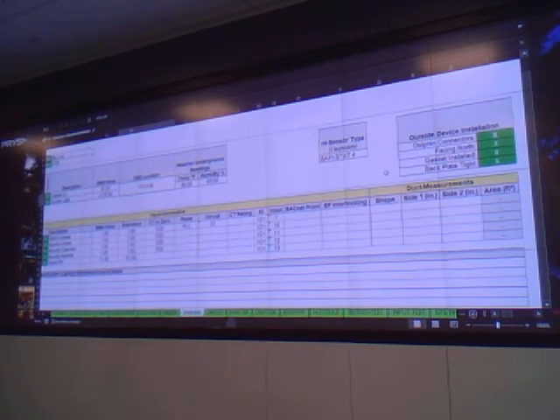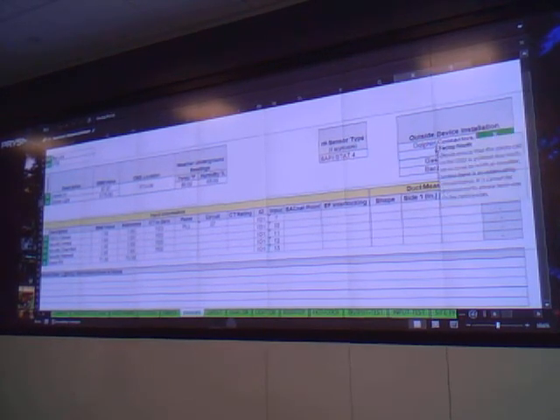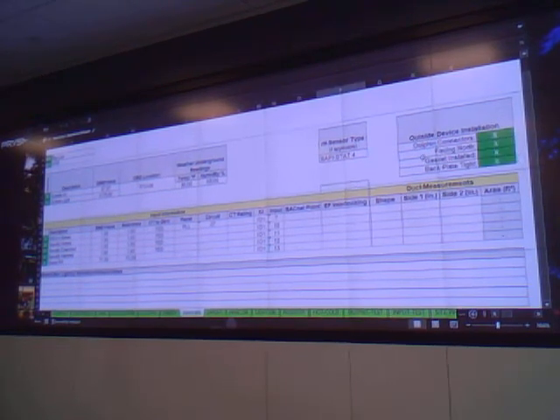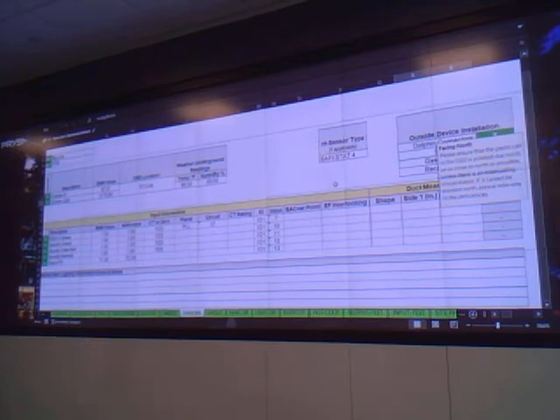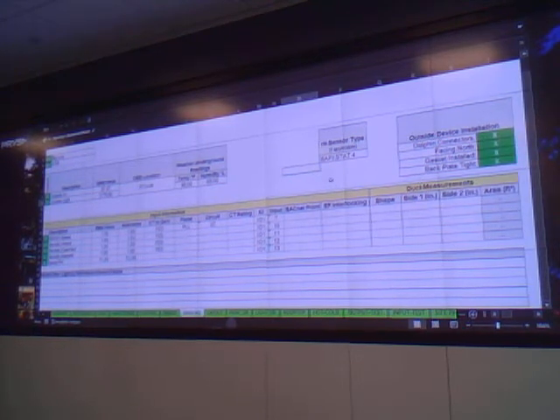You do color for color, but what you're going to do is you've got 2 ends to the RTU. One end's got your condensation fans, and your evaporation fans up in the unit. We want to be on the opposite end, I don't want that hot air blowing on that. That's why if you look here, there's also a verification backup for Weather Underground. You hit Weather Underground and verify that those readings are pretty close to what we're reading. See right there? That's outside temperature and humidity.